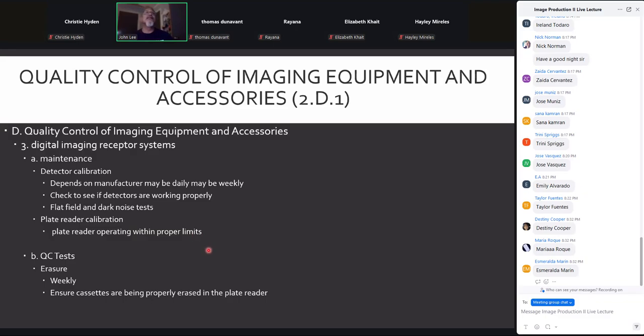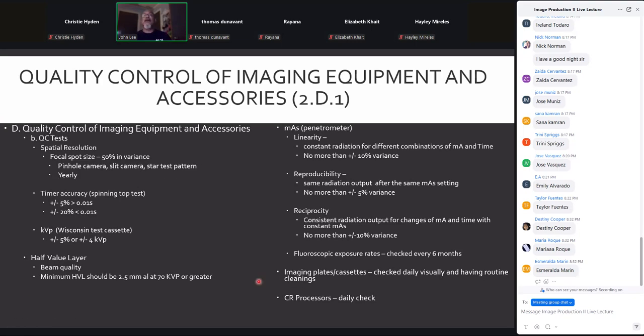Detector calibration depends on the manufacturer and what they prescribe. It can be daily, it can be weekly. This is just to make sure that the detector itself is operating properly, including doing a flat field and dark noise tests. For CR, we want to have a plate reader calibration. QC tests for erasure on CR should be done weekly. Cassettes should be cleaned on a regular basis as well. Check daily visually, and have routine cleanings.